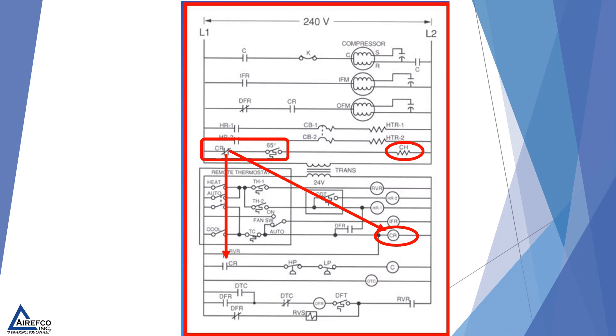The contact completes the circuit through the 65 degree temperature sensor. So if the temperature is at or below 65 degrees, the crankcase heat in the off cycle will be energized.